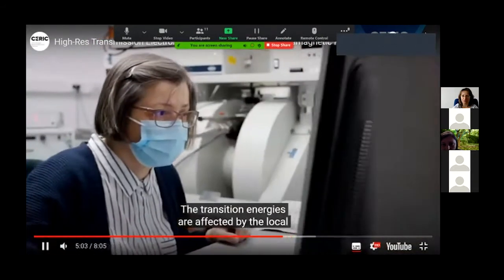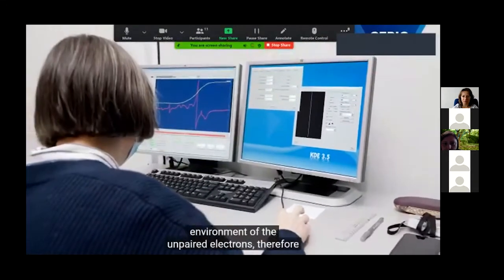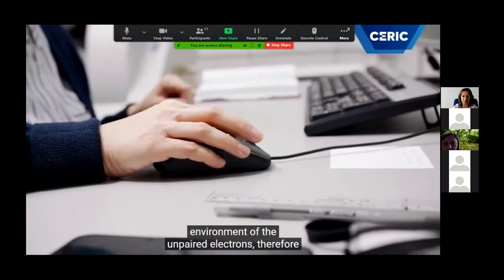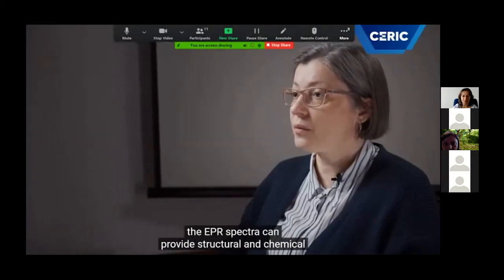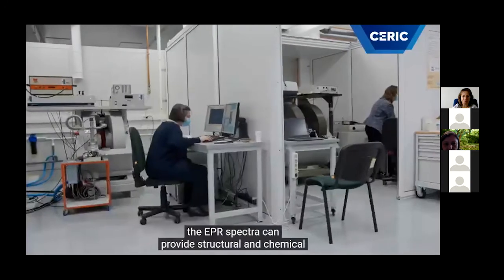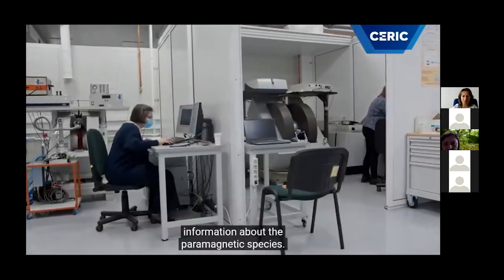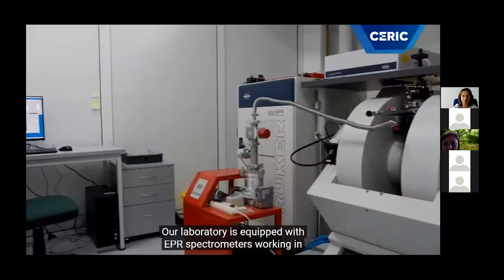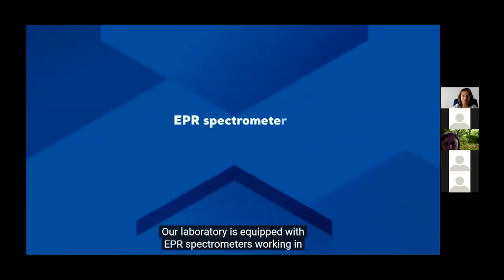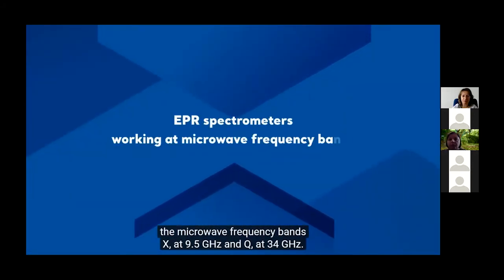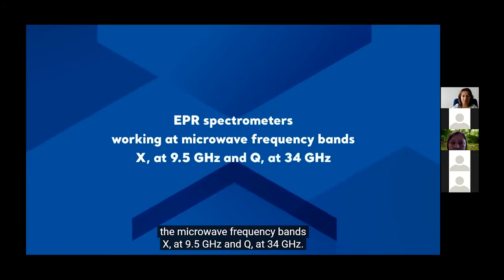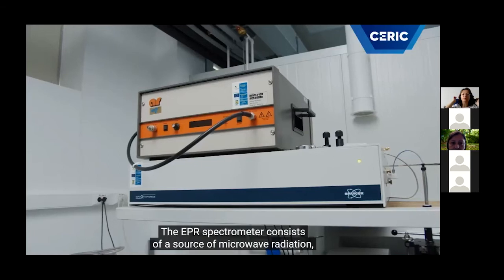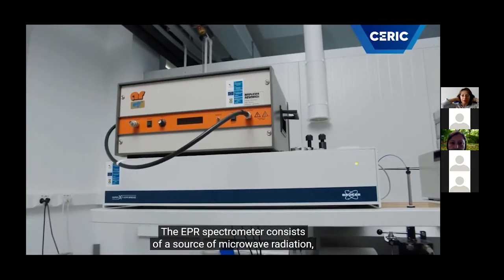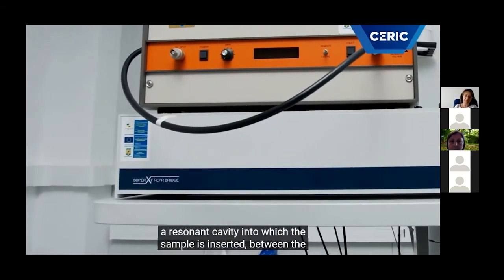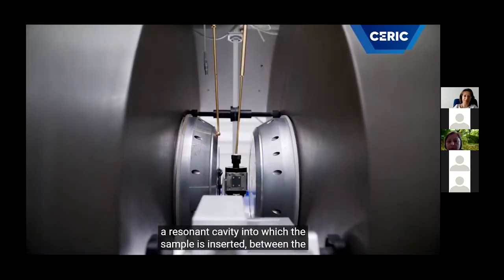The transition energies are affected by the local environment of the unpaired electrons. Therefore, the EPR spectra can provide structural and chemical information about the paramagnetic species. Our laboratory is equipped with EPR spectrometers working in the microwave frequency bands X at 9.5 GHz and Q at 34 GHz.